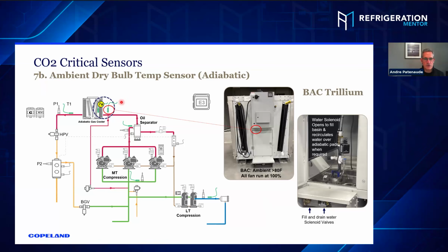But when you look at those sensors, one of the things I was trying to figure out is where they're all located, a little bit different. This is a BAC gas cooler, and below the electrical panel, there's a little area here where that ambient sensor is, protected from the sunlight. So it's only measuring ambient there. And as I mentioned, at 80 degrees and above, all fan speeds are 100%. When you open up this little cabinet here, there's a basin down here that, when it reaches the right temperature, fills up with water, and the circulating pump is really what sends the water up onto the pads. And you have your fill and your drain solenoid valves at the bottom of these BAC gas coolers. But that 80 degrees is that point. Yep.